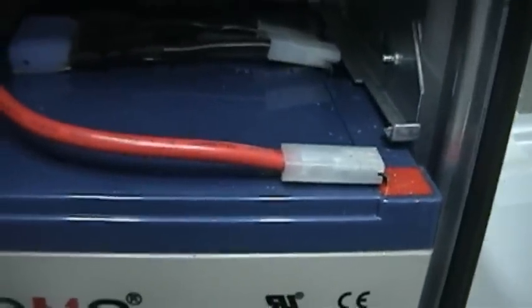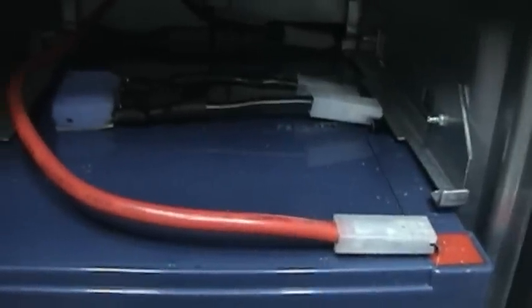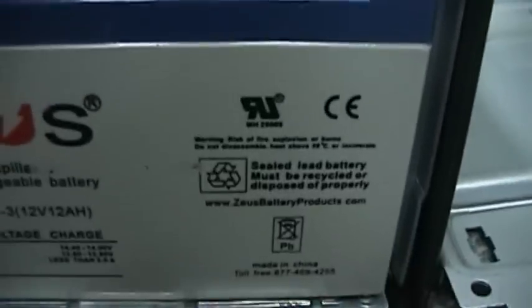I would imagine the framework is the same basic metal form for all of these units. As you can see, although this unit is just 500 volt amps smaller than its sibling down in the basement, it's also got quite a bit smaller, lighter wiring, and not as heavy a connection at all the contact points compared to the larger unit. But there's still an inline fuse.